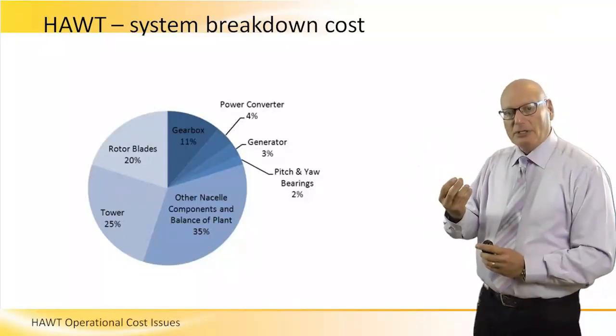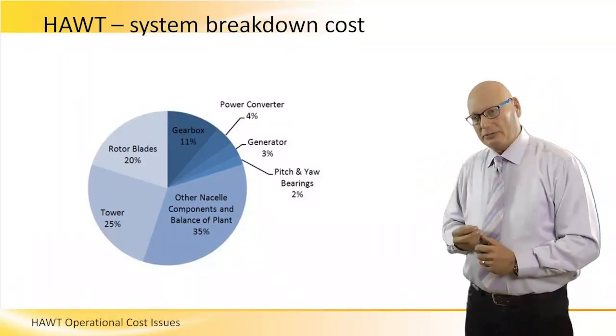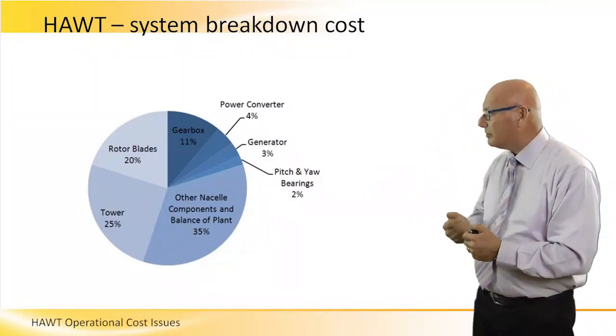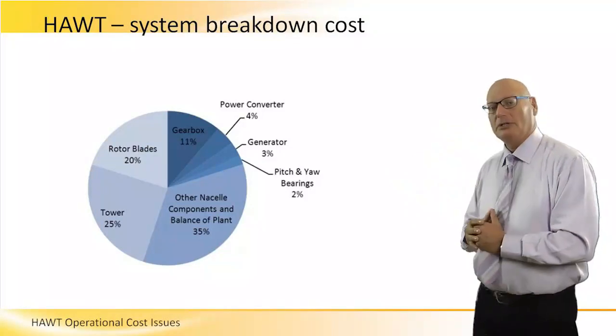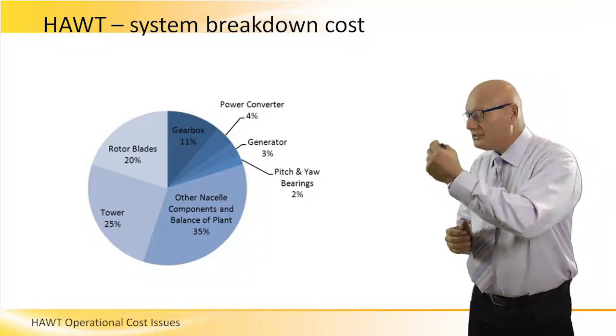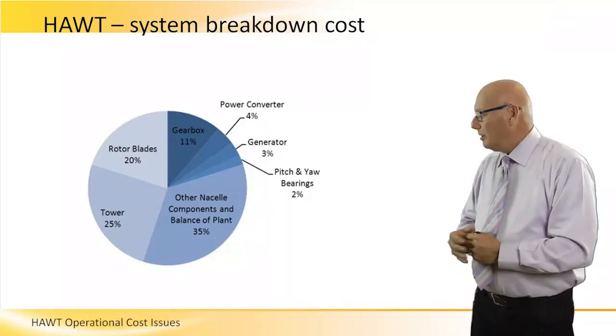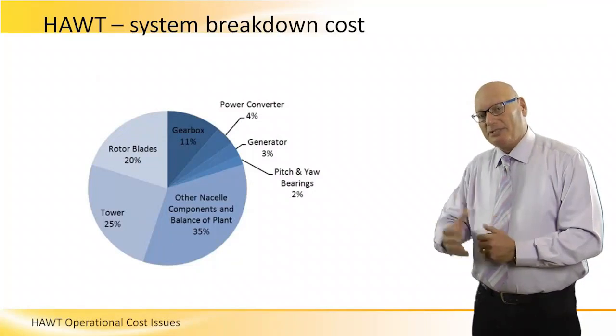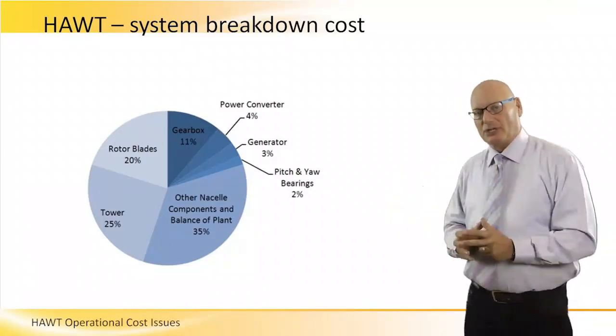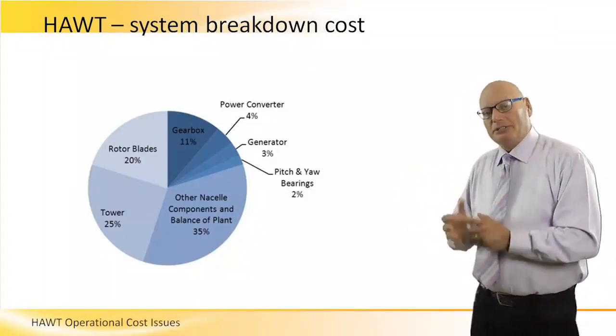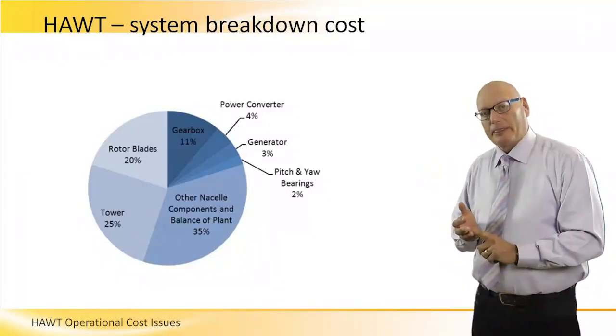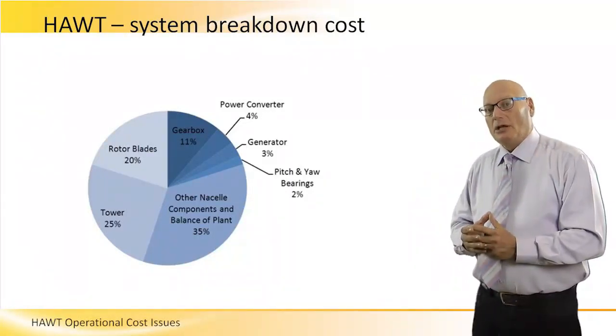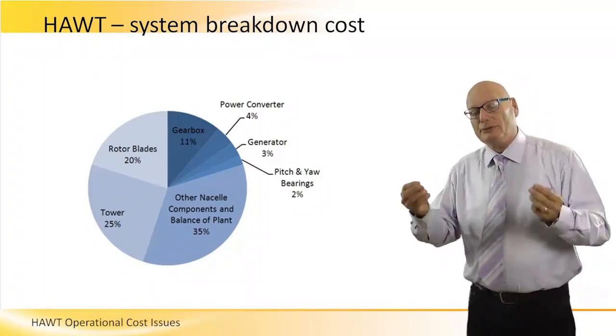Evaluating system breakdown cost by component, rotor blades contribute 20% to breakdown cost. The tower itself contributes 25% — more than the rotor blades. The nacelle components and balance of plant account for 35%, where the more sophisticated systems reside: the generator, brakes, all control systems, the gear and gearbox. So it's 35% compared to 20% for the rotor blades — rotor blades are very reliable devices.